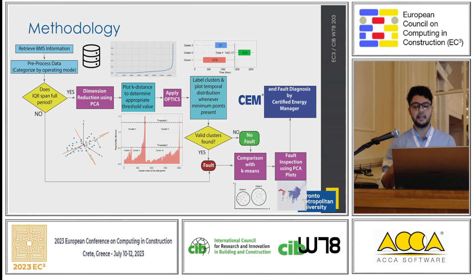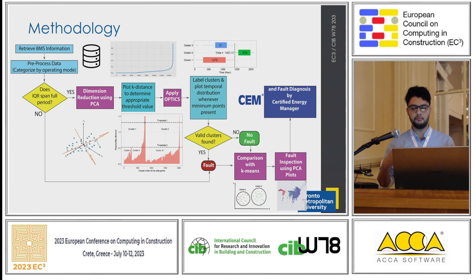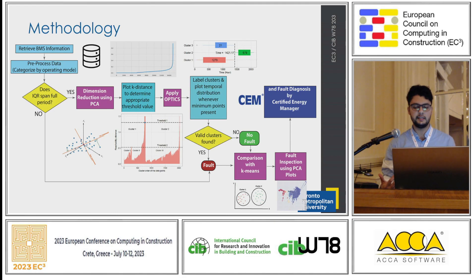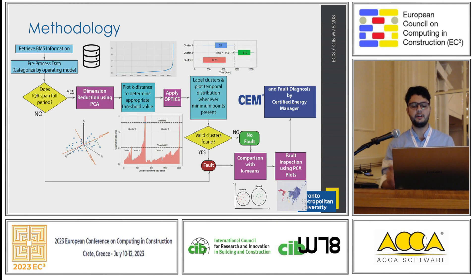We need to consider that data in different operation modes may result in the existence of different clusters. So when we get data from the BMS or BAS, we need to categorize the data into different subsets according to the operation modes of the HVAC system — for example, whether the system is on or off, heating operation, cooling operation, or natural ventilation. In this study, we calculated cooling energy for each data point and used operation data with calculated cooling energy within the interquartile range, which represents the most concentrated observations.